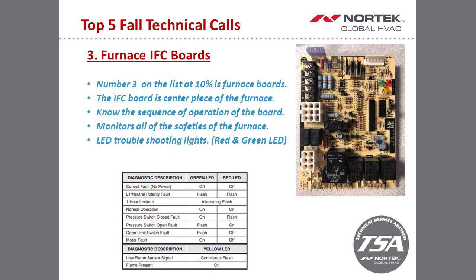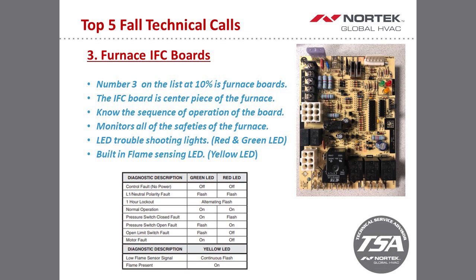Also, on the board, we do have a yellow LED, which is there for your flame sense. So under a normal circumstance, that should be a solid yellow. If you're in a poorly lit room, that light may appear to flicker a little bit, which is fine. If it's actually flashing on you, meaning it turns off and then back on, off and back on, that would indicate to you that you have a low flame signal, which generally will be under 1 microamp DC. So if you have that scenario, it's probably just a dirty flame sensor, and we just need to clean that up with either some steel wool or Scotch-Brite works good too. Just don't use sandpaper. That's one thing we tell guys not to do. Again, your yellow and the red and green LED should be a solid on the whole time of the furnace operation.